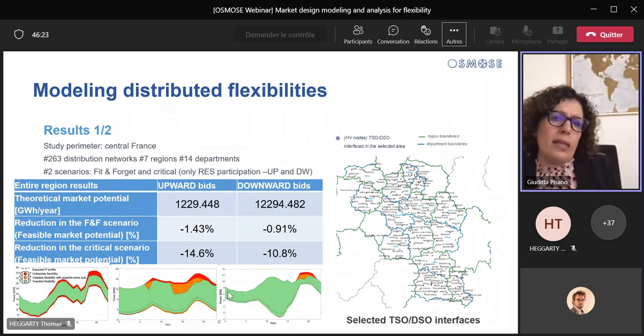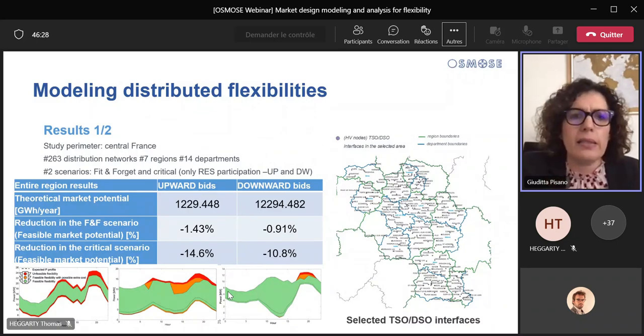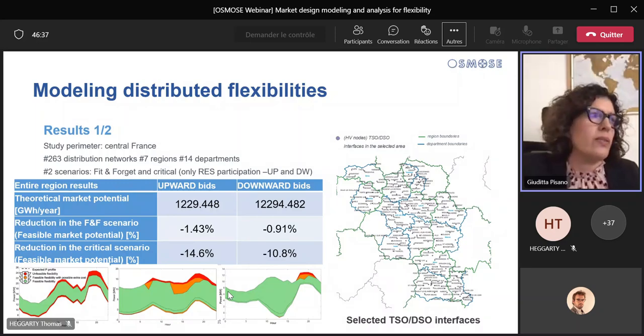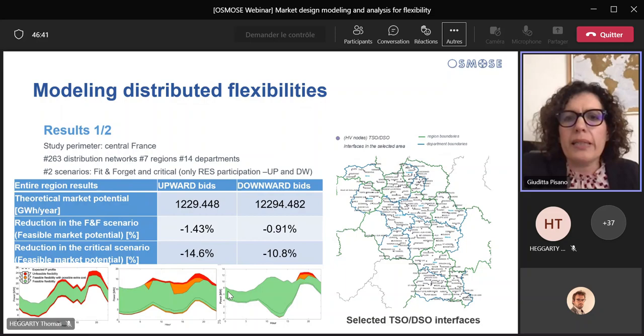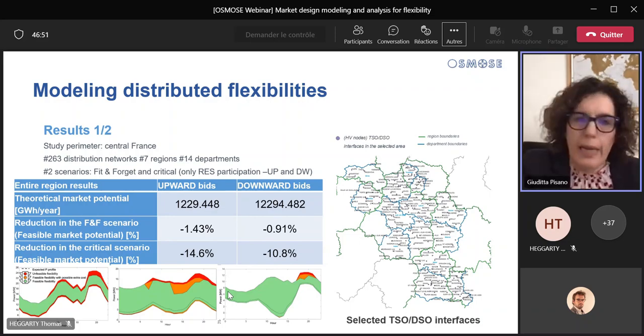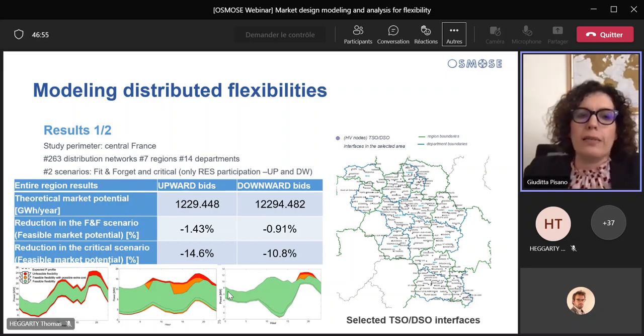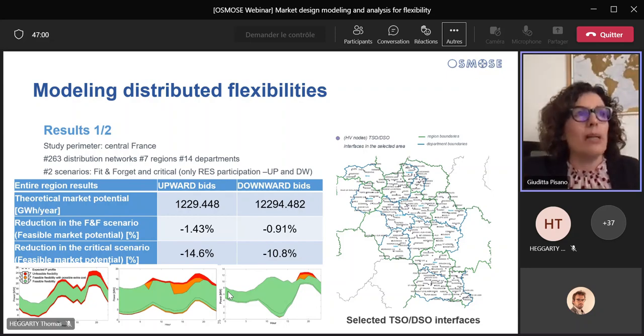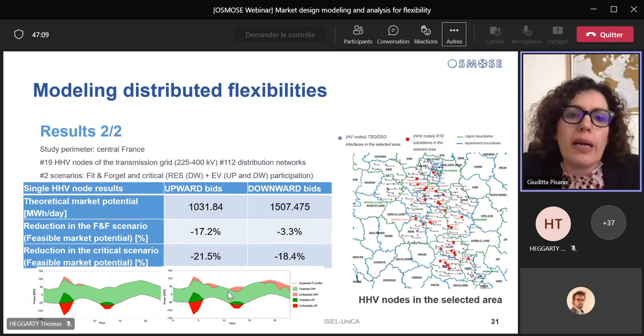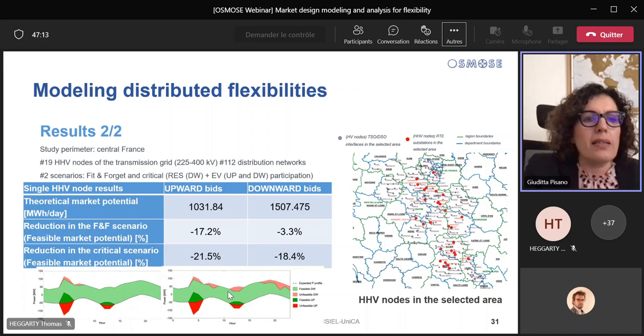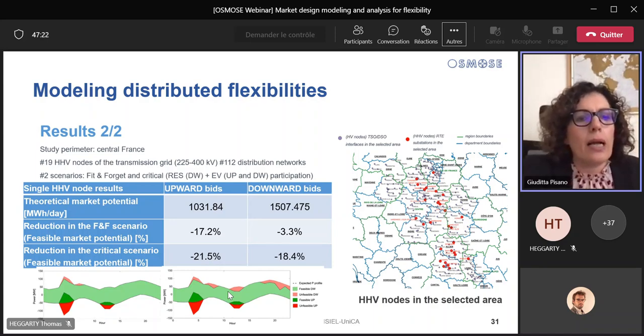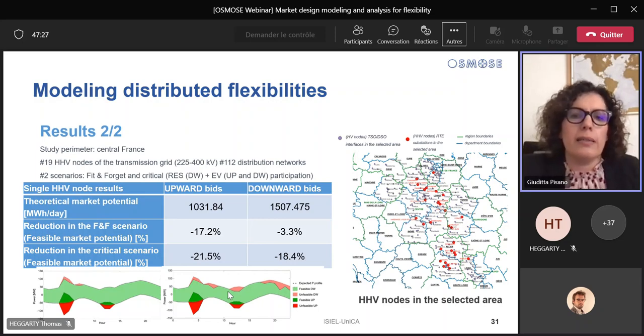Now only a taste of the results of our studies. In this slide, the results of an interior selected region in central France. Two scenarios were simulated: one with DRs spread along the distribution network according to the fit-and-forget approach, and one more critical with big size resources concentrated in a few nodes of the networks. In the critical scenario, the reduction of the theoretical market potential is, as expected, more significant than in the fit-and-forget scenario. These results demonstrated that the grid limitation of the distribution network cannot be disregarded. The same consideration can be made regarding the results of a single HHV node that combines several distribution networks — the spatial downscaling reveals local criticalities and the reduction of the potential is greater.